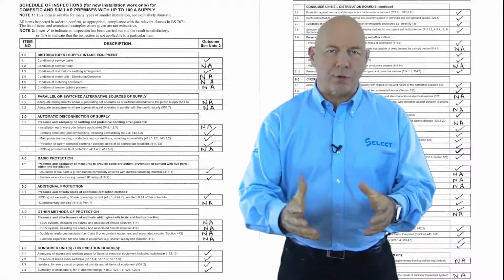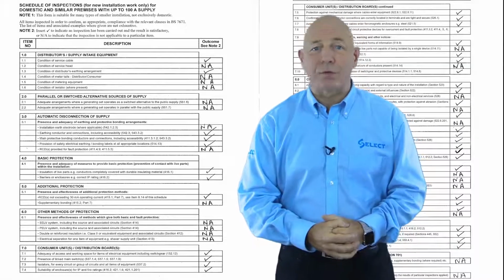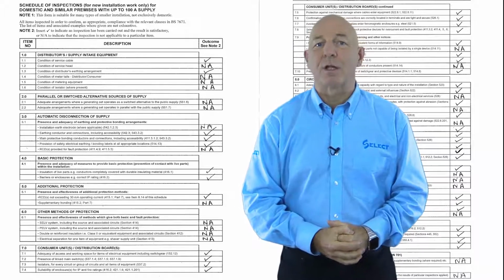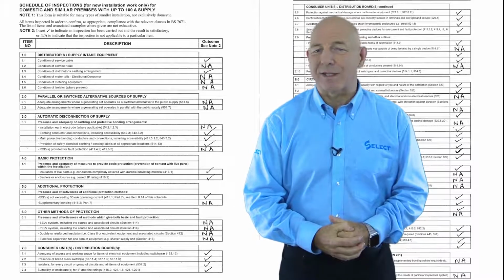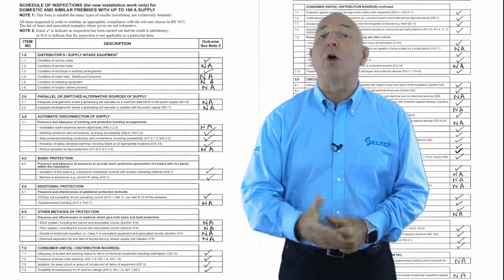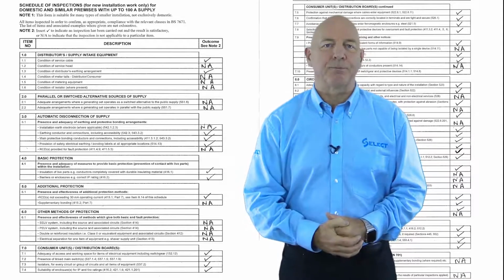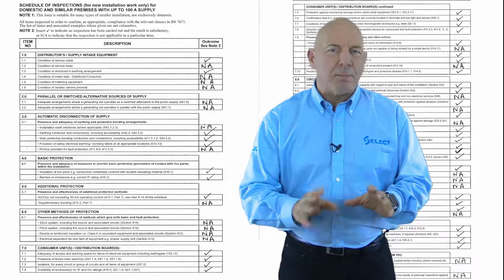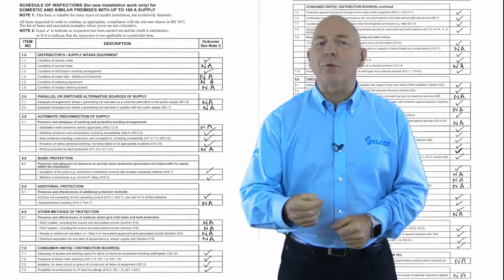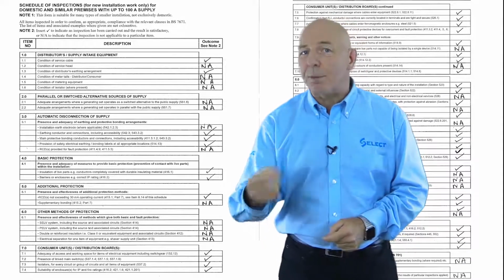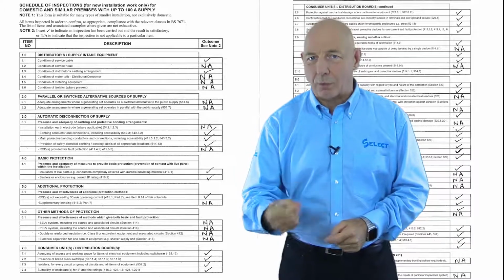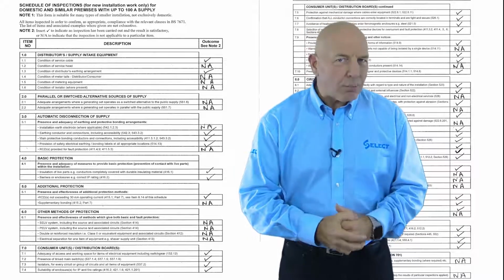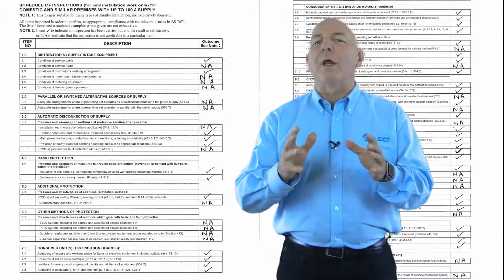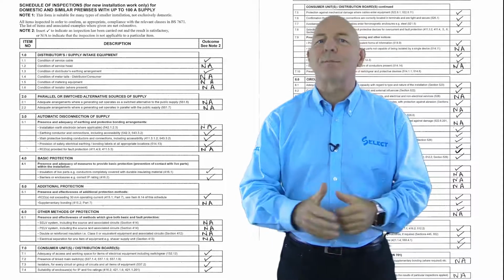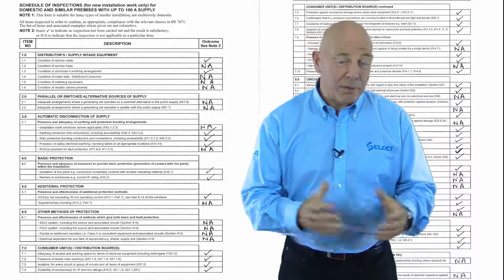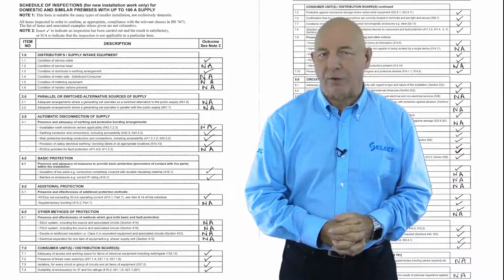Now, it's important that defects or omissions revealed during the inspection and test process are made good to allow the necessary documentation to be issued on completion of the verification. Inspection may be relatively straightforward in the situation where the inspector is the person who's carried out the installation work. However, it may not be so straightforward a task when he or she has to inspect the work of others, particularly on larger installations.